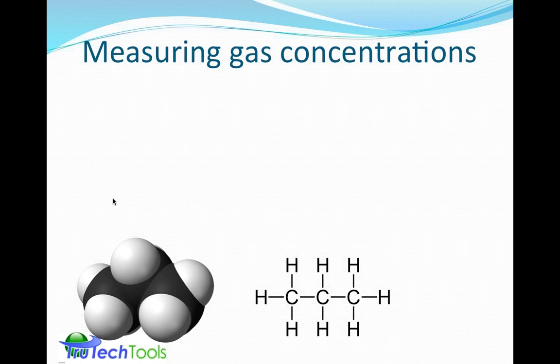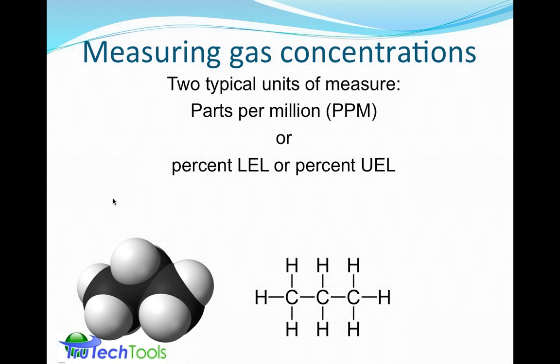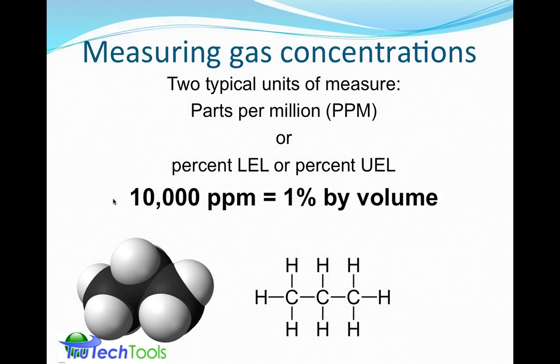When it comes to measuring gas concentrations, we're showing here C3H8, which is propane. The typical units of measure are parts per million, or percent LEL or percent UEL. And usually it's percent LEL because we want to stay on the safe side in that green zone and stay well below the area getting into the red zone. However, concentration of gas is measured in percent by volume. So 10,000 parts per million is 1% by volume. The parts per million is percent gas, but the LEL depends upon the type of gas. So the LEL concentration will be different for different types of fuel gas. Again, the two major ones, methane and propane, with 10% LEL being 5,000 ppm methane and 10% LEL being 2150 ppm propane.